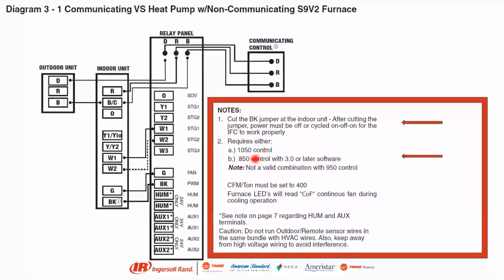And for the BK, you have to have the 1050 or the 850. CFM must be set at 400 also with the S9V2s. S9V2s, the factory default is 350 per ton in cooling. So you have to get in the menu and change that to 400 CFM.